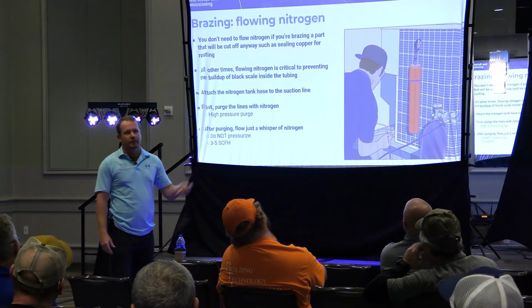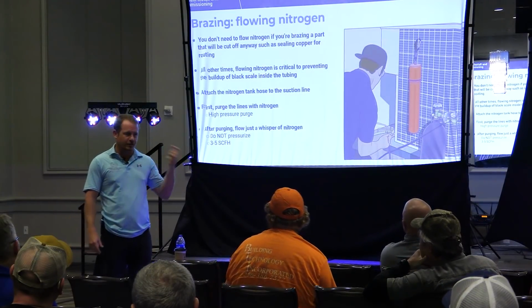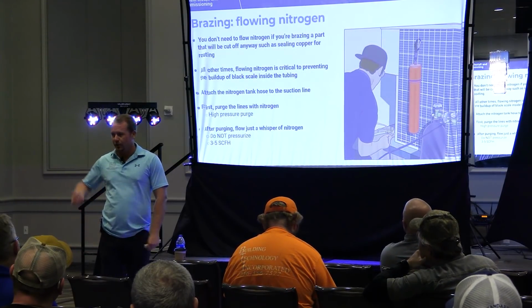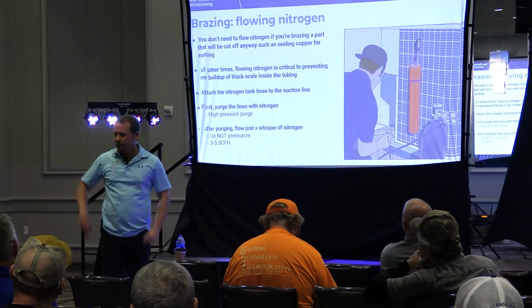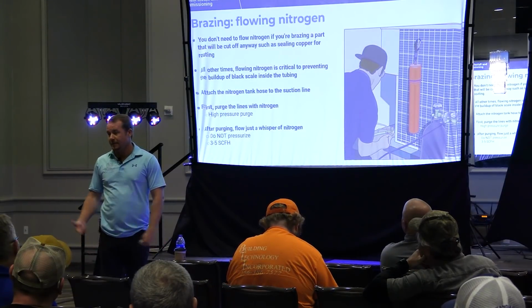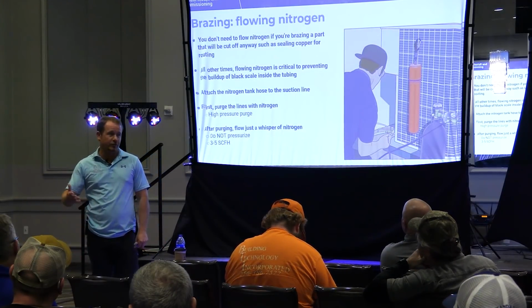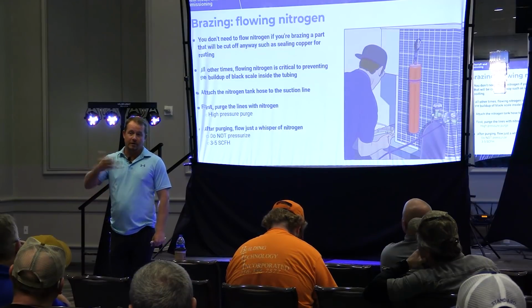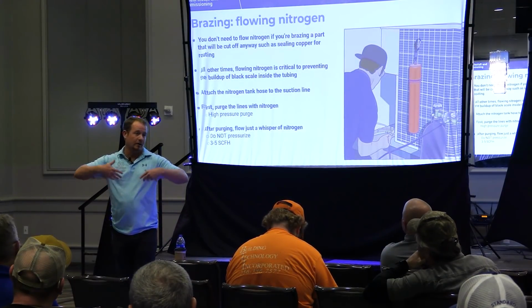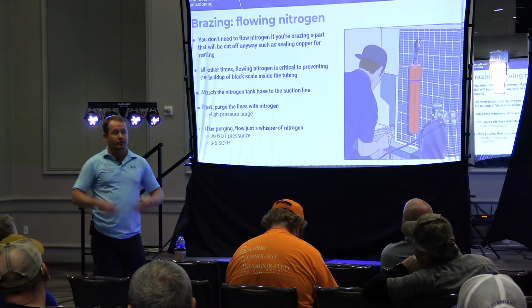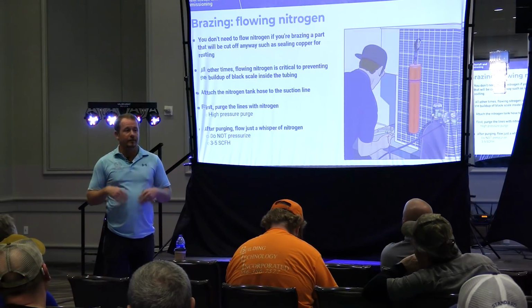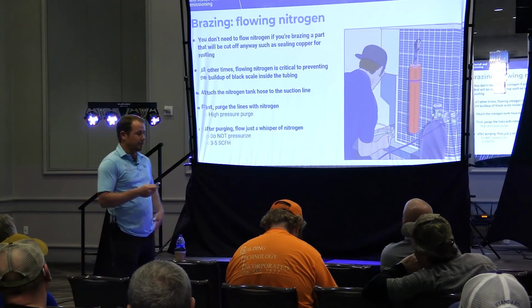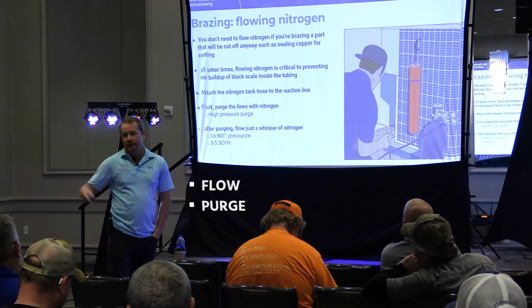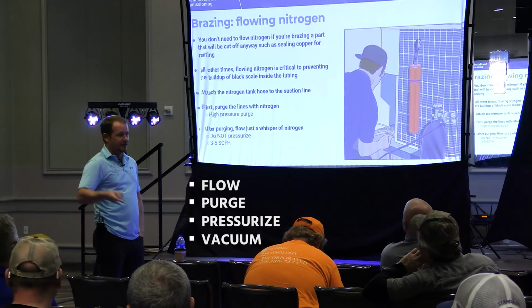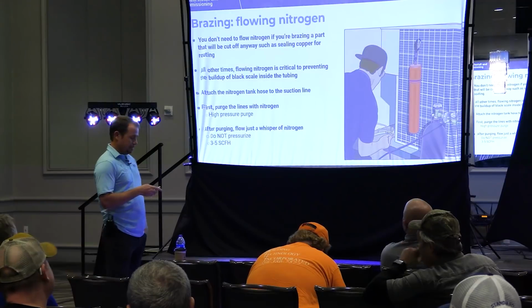Using a purge as part of your pre-process before you pressurize is good practice anyway - that's nothing more than letting it purge through a little bit, then stop. It makes vacuums a lot better, even on systems that aren't old. As you put in a new compressor or change a component, do a purge, then do your flowing, then purge, then pressurize, then vacuum after the pressurization.